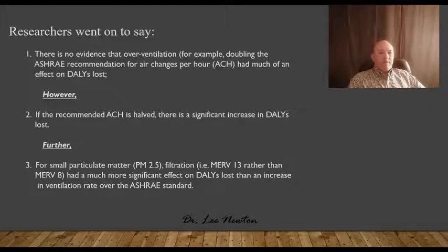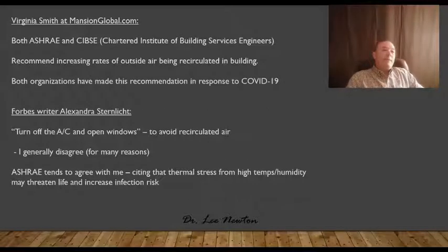Now, the studies also showed that for really, really small stuff, PM 2.5 or smaller, an upgrade in filtration, in other words, a MERV 8 going to a MERV 13, had a much more significant effect on DALYs loss than an increase in ventilation rate over the ASHRAE standard. We're going to probably contradict that information here in a moment, not the filtration, but the ventilation. Virginia Smith at mansionglobal.com summarized some information from both ASHRAE and CIBSE, which is the Chartered Institute of Building Services Engineers. We're talking about the COVID-19 pandemic.